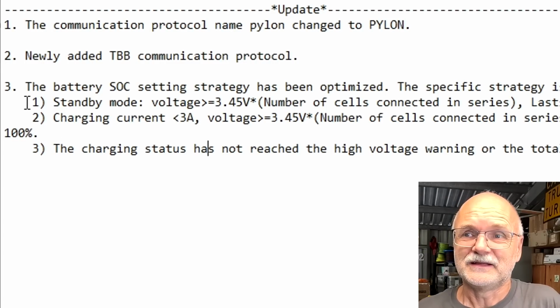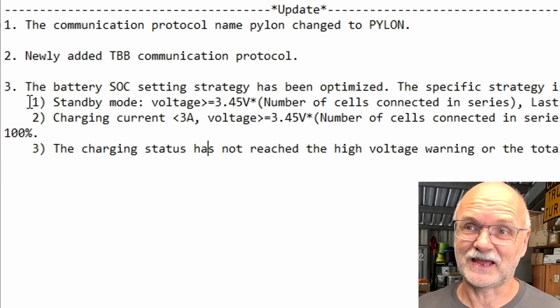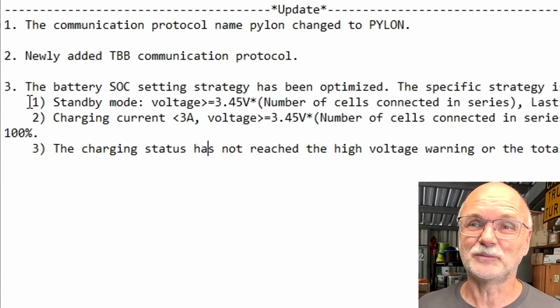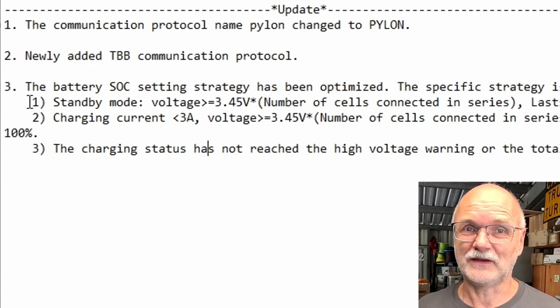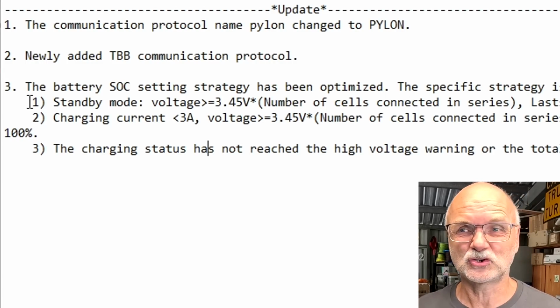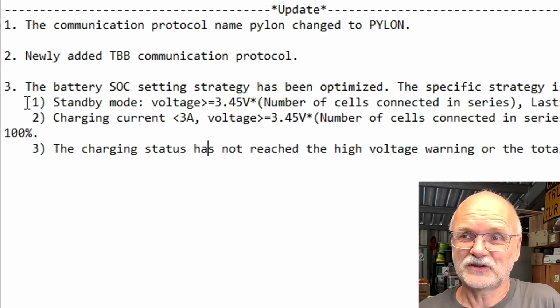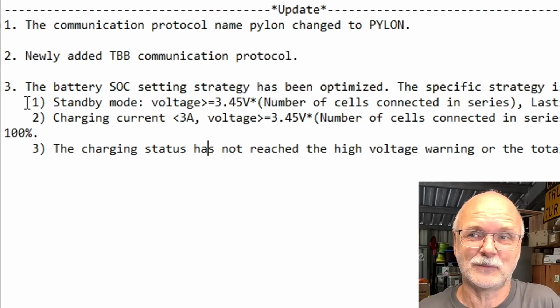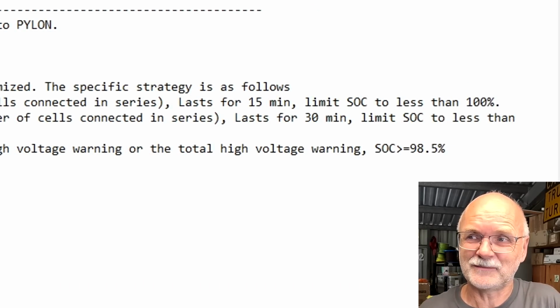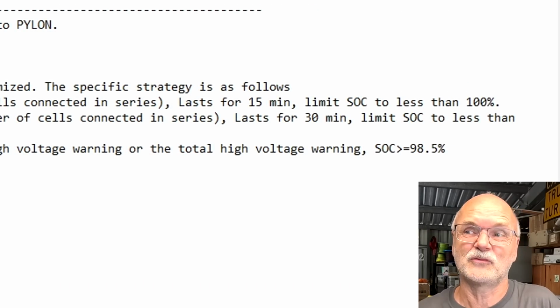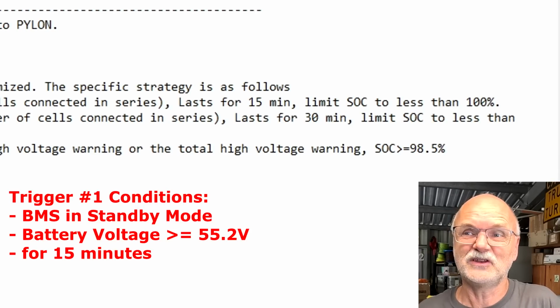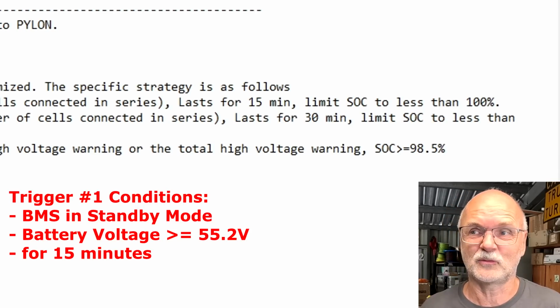First option, standby mode. So why does it say standby mode here? The BMS needs to be in standby mode for this, meaning no charge going in, no charge going out. The voltage is equal to or higher than 3.45 volts times the number of cells, so battery voltage needs to be higher than 55.2 volts. This lasts for 15 minutes, and the BMS will then reset to 100%. So you need to be over 3.45 volts for 15 minutes, and it will reset to 100%.